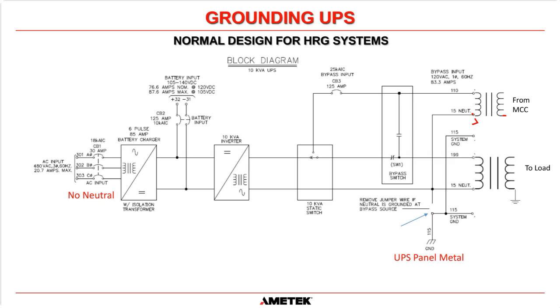But in this circumstance, what we have to do, and what all high resistance ground systems do to allow a ground connection at the final load destination, is that a high resistance ground usually always uses transformers to feed their critical loads, and the secondary of that transformer is what is used to create the ground path. Okay. So in truth, once again, the jumper would be removed here.